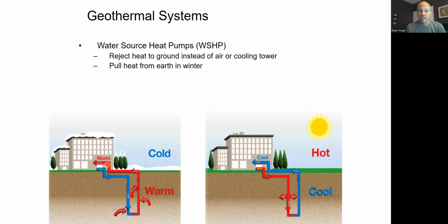Or vice versa. Let's say, and this is more common for where we live, we're taking more heat out of the ground in the wintertime. So instead of starting the season with 70-some degree ground temperature, I'm starting with 60-something. And the next season, I'm starting with 58. The next season, I'm starting with 56, because I'm taking more out of the ground than I'm replacing in the summertime. So what happens in these scenarios is whichever one is more dominant, I need something to take care of the rest. Let's say it's a heating dominated building. That means I'm going to have this ground loop and a small boiler, gas fired or electric, that is going to be supplementing this loop.